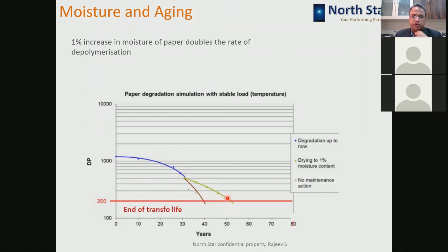So a transformer which is normally living 30-35 years can live up to a life of say around 50-55 or even 60 years. So a well-maintained transformer can serve you over a period of 60, 70, even 80 years also. There are some transformers, somebody was telling me yesterday, it is a 100-year-old transformer, it is still working.